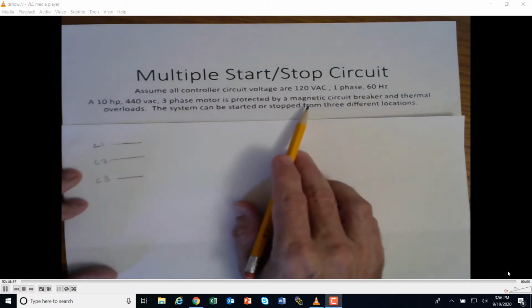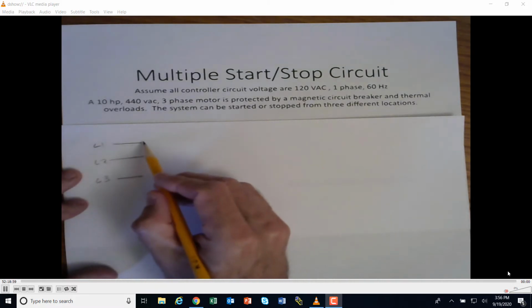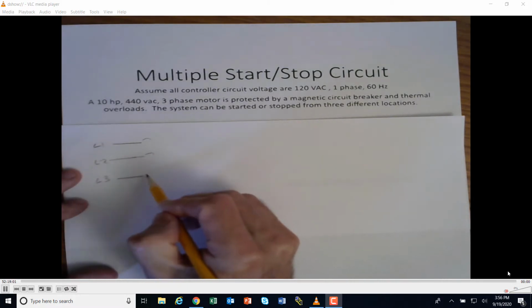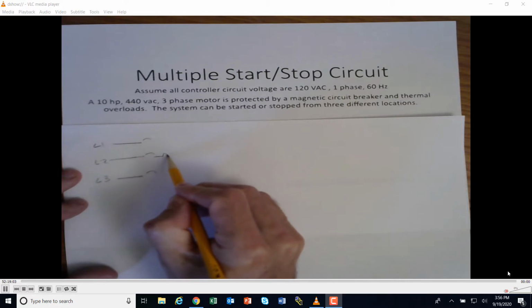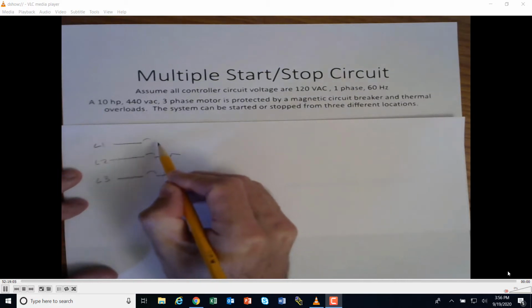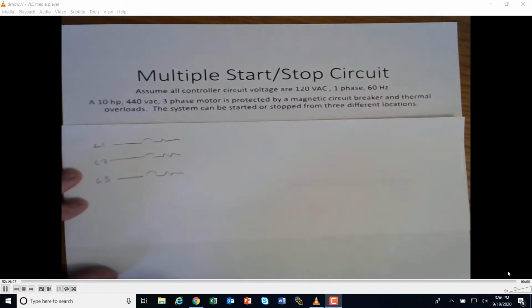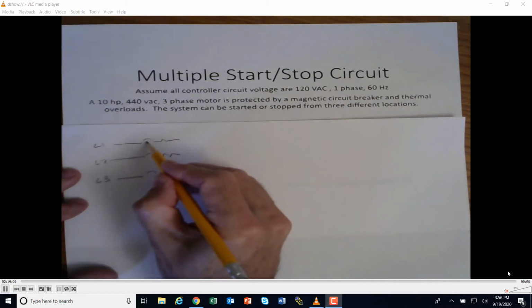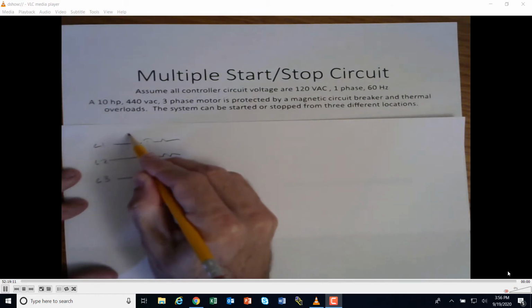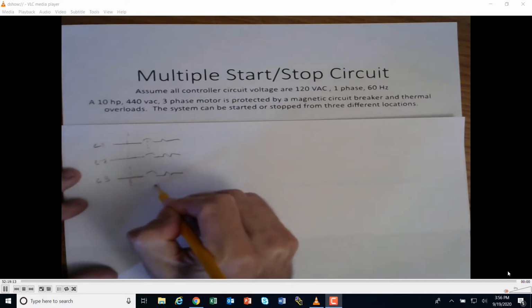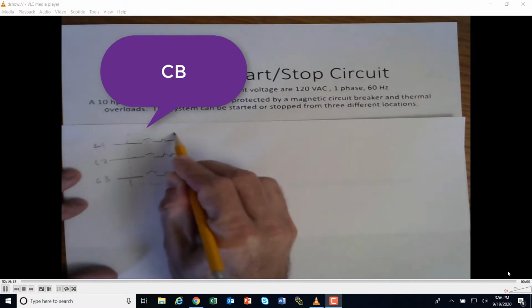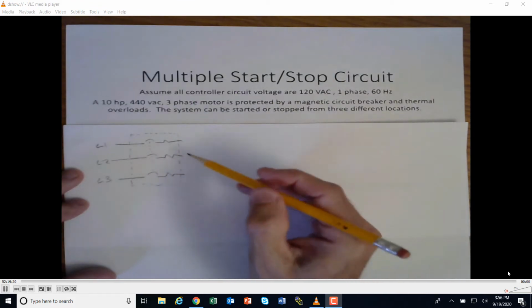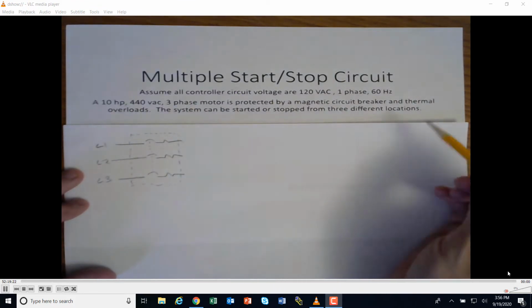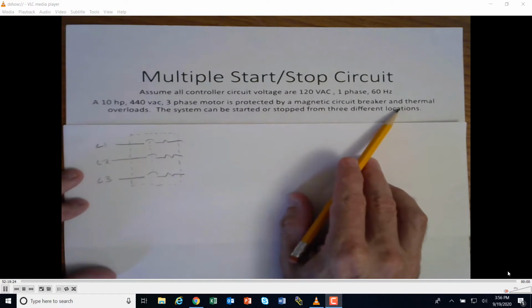That's our power, and it's high voltage, in this case 440 VAC. It has a magnetic circuit breaker. I'm going to draw my protection here, put a dot between here, and enclose it like this. So if I looked at this device, it means this is all one device, a magnetic circuit breaker, and there are thermal overloads.